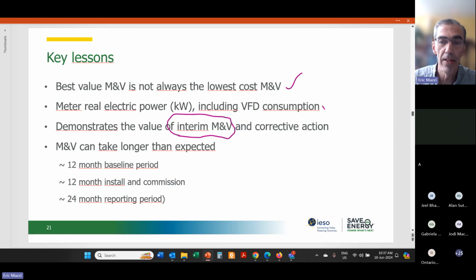It's just backing up. Another basic lesson is it's important to measure real power. Make sure you capture the VFD or any important load in a system. This M&V took a long time, and not a lot of people have, let's say, the patience for that or would appreciate the value of doing that. It doesn't mean that there's a lot of activity and chewing up a lot of hours over the 700 and some days of the reporting period.